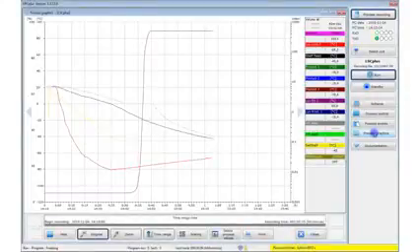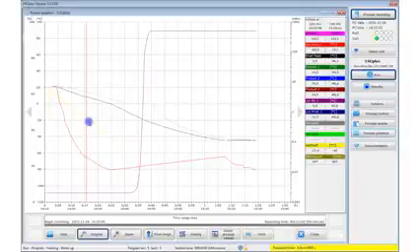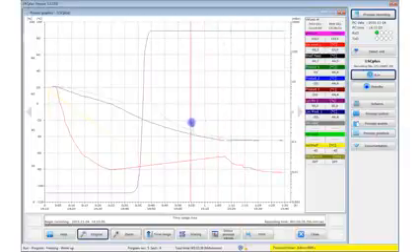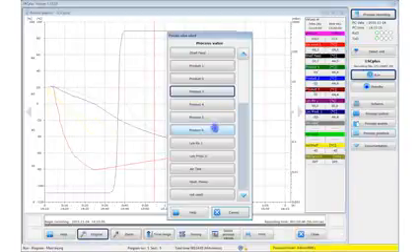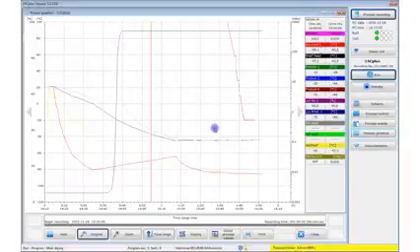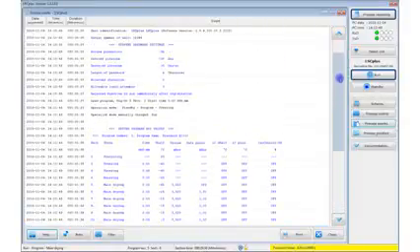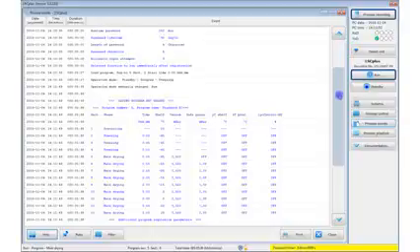To view the numerical values at a particular time point, click on the process graphic. A red cursor line appears and the table shows the process data at the selected time. You can move the cursor line anywhere in the process graphic. You can configure the parameters to be displayed in the process graphic and the table. This allows you to view and monitor significant process data during the process time. Along with the process graphic, the software can display a process events list containing all data related to the system and the process, along with all messages and alerts with corresponding timestamps.